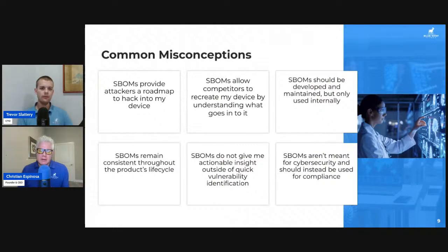Yeah, the licensing you brought up is important because isn't there a situation where if you use certain third-party libraries, you may have to disclose your source code? Yes, and I will note that this is less common now. Recently, in the past 5 odd years, the prevalence of copyleft licenses, which do require you to disclose your source code, are very, very uncommon. Having said that, the average development time for medical devices is quite long. And so we often see development extending past 7 years for medical products. They're using a lot of old embedded systems where these licenses may be a lot more prevalent. So it is still a very relevant concern in tightly regulated industries where development takes a very long time.